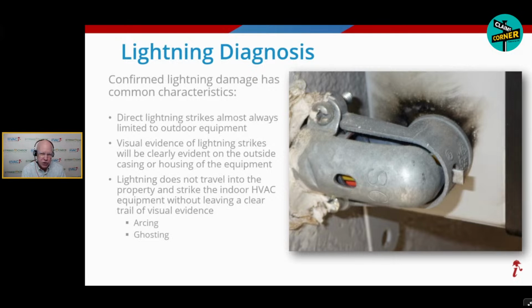Again, surge will not do that. Surge will be in the wires. So what's happening is it's traveling through this conduit. If it's coming from the left here and making that left hand 90-degree bend, there was a small gap between the conduit and that metal plate on the equipment. When the lightning energy tried to jump that gap, it ghosted out. That's the term they use. If you had been standing there, you would have seen a little flash and a little poof, the energy going into the air. So if you see ghosting, which is usually between metal products or where metal ends into something else, you're pretty confident you're looking at lightning damage. I would try to validate other things on the property, but it's pretty likely lightning if you're seeing ghosting. Hopefully that's a new term for you today.